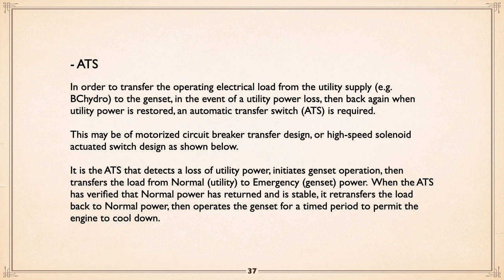So fundamentally, when it goes to transfer, the power is dead on the line. If it goes to transfer over to emergency, there's a little motor that will move it, because you've got emergency supply. The generator has seen the power failure and started, so you do have power there. So a little motor will drive the circuit breaker mechanism, disconnect offline, and then reconnect to the generator, bang, and away you go. Same thing coming out of it: you have to disconnect and then reconnect. And because of how you're powering it, it takes a few seconds. So there's a delay between the two with the motorized.